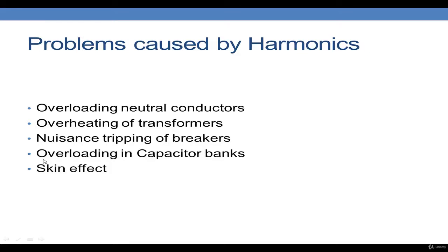Harmonics can also cause nuisance tripping of breakers. All circuits contain capacitance and inductance, which have one or more resonant frequencies. When a resonant frequency corresponds to a harmonic frequency produced by a nonlinear load, harmonic resonance can occur. Depending on whether the circuit is a series or parallel circuit, this results in voltage amplification or current multiplication, causing nuisance tripping and damage in the power system.